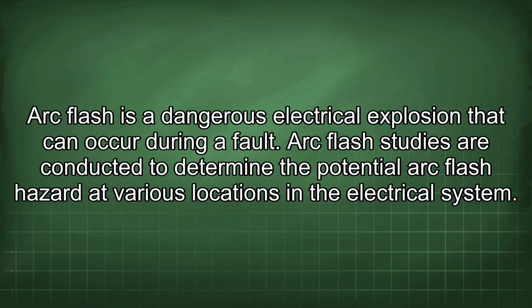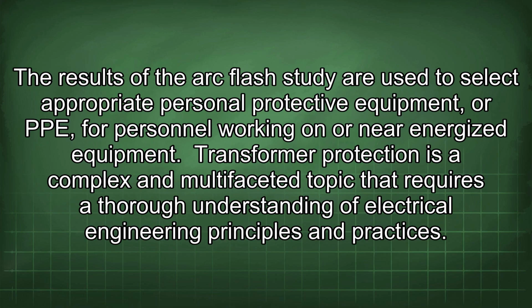The concept of arc flash hazard is also relevant to transformer protection. Arc flash is a dangerous electrical explosion that can occur during a fault. Arc flash studies are conducted to determine the potential arc flash hazard at various locations in the electrical system. The results of the arc flash study are used to select appropriate personal protective equipment, or PPE, for personnel working on or near energized equipment.